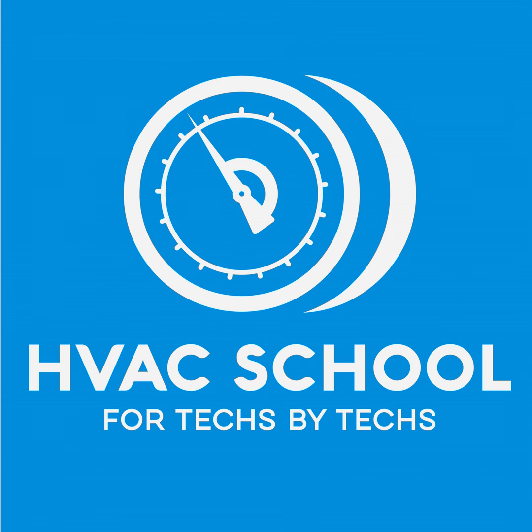Yeah, that's huge. And when you talk about design conditions, this is a moment for us to pause and remind everyone that this is not just true of VRF, VRV. This is true of all equipment. If you're using AHRI conditions, which AHRI design conditions are 95 degree outdoor dry bulb, 80 degree indoor dry bulb, and I think it's 50% relative humidity, those are not realistic conditions for the majority of the United States. And so you have to make adjustments.